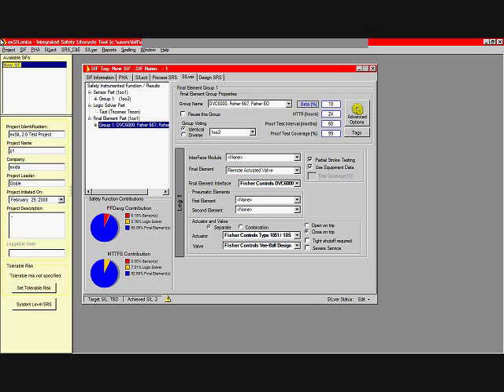So what I have to do is go in and do some very detailed common cause analysis, see if I can reduce the beta number, and if I can't, then I simply must reduce the proof test interval, or find a... That's about it. So, point, SIL 3 is hard. SIL 2 is a lot easier.